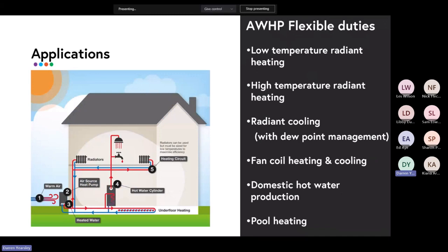Okay, so air to water heat pumps, one of the advantages in multipass anyway is these flexible duties. From one appliance, you can do a multi-use system where you've got low temperature radiant heating, like underfloor heating, for instance, high temperature radiant heating through radiators. We can operate 65 degree flow and send them to the radiators, no problem. We can also do radiant cooling, which is a new technology which we've brought to the market. It's got automatic dew point management to avoid condensation on the radiant surfaces.